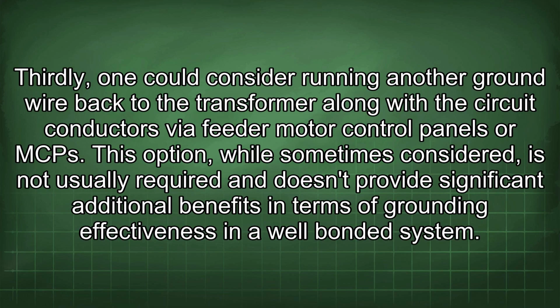Thirdly, one could consider running another ground wire back to the transformer along with the circuit conductors via feeder motor control panels, or MCP. This option, while sometimes considered, is not usually required and doesn't provide significant additional benefits in terms of grounding effectiveness in a well-bonded system.